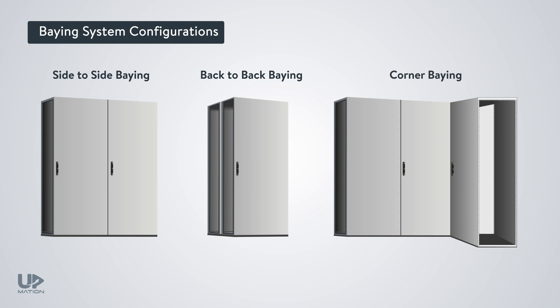As you see here, depending on our requirements, there could be other baying system configurations as well. In these systems, as all of the enclosures are connected to each other, they have potential equalization and therefore provide more safety, and we do not have to earth each of them individually.